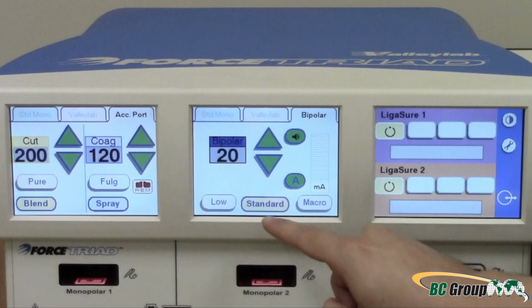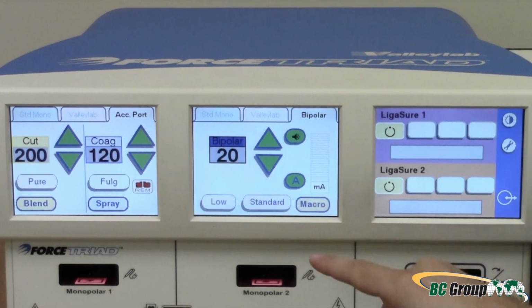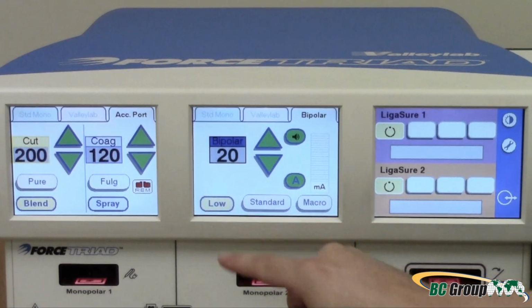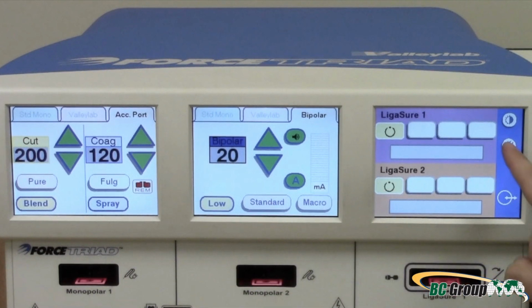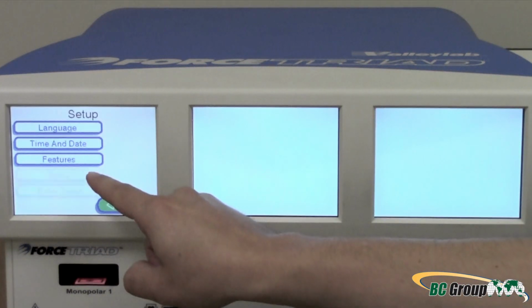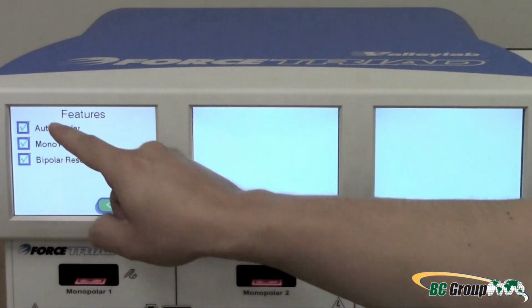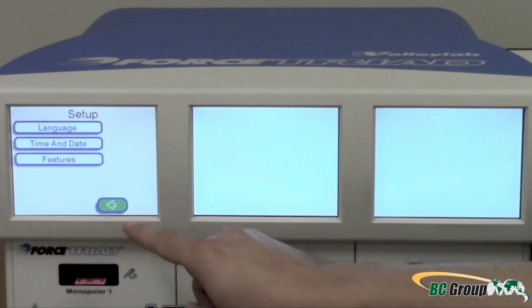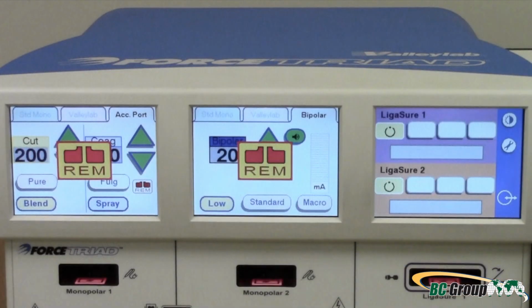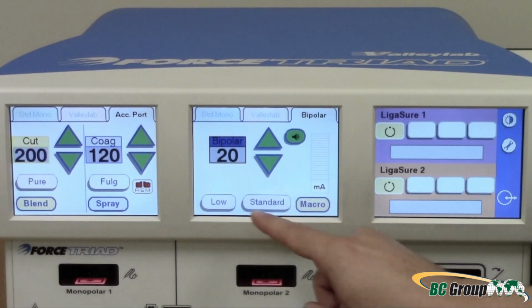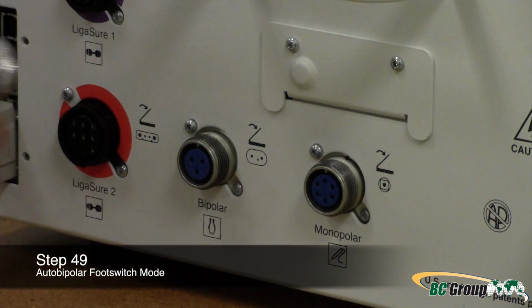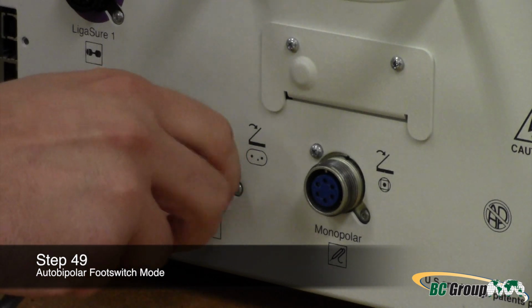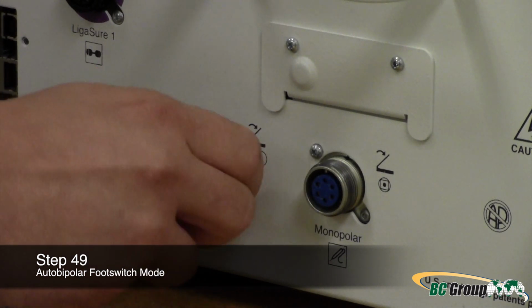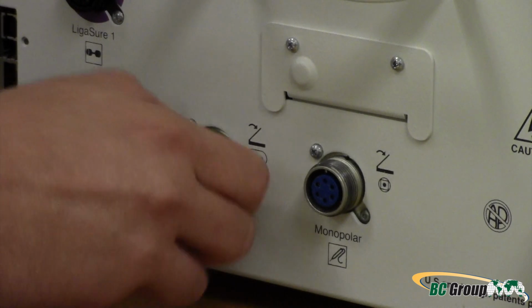Verify that the autobipolar function is available in the low, macro, and standard bipolar modes. Verify that the power setting does not change when the auto button is active or inactive. Step 49. Autobipolar foot switch mode. Connect the foot switch or foot switch simulator to the back of the generator.